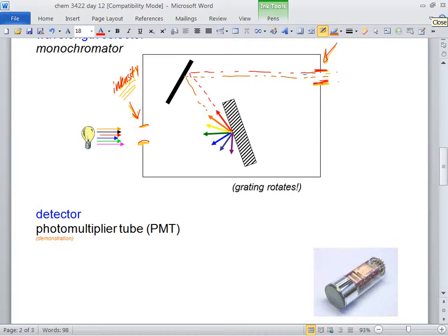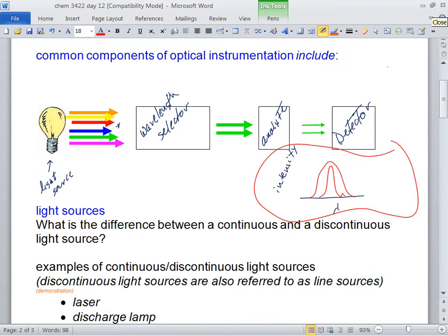And you can control those slit widths. What did you say that second slit width controls? The technical word would be bandwidth. What they mean when they say bandwidth is go to the half height of this thing. Let's pick one peak. Go to the very half height and see how wide that is. How wide is it in nanometers? Full width, half max, FWHM. That's more information than you need, but I would say that second slit controls the full width, half max. Now, actually, they both have a big effect on it, but that second one really does, much more so, I think, because it's after the grating.